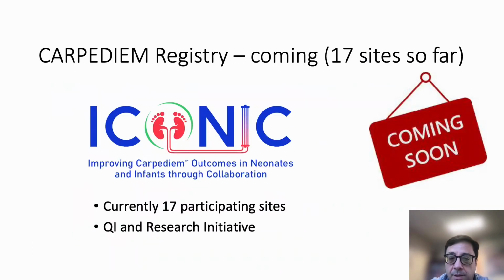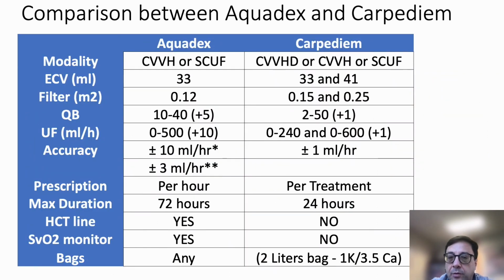There's also a registry currently being performed. 17 sites are participating in the United States to do QI and research called the Iconic Registry, and that is coming soon to you. And so to compare Aquadex and Carpe Diem, they have similar extracorporeal volume. Aquadex could be done CVVH or just ultrafiltration. Carpe Diem, you could do dialysis or replacement, but not both, or just ultrafiltration. Again, similar extracorporeal volumes. Blood flows can be 10 to 40 versus 2 to 50. Here you can calibrate by 1s in the Carpe Diem, by 5s in the Aquadex.